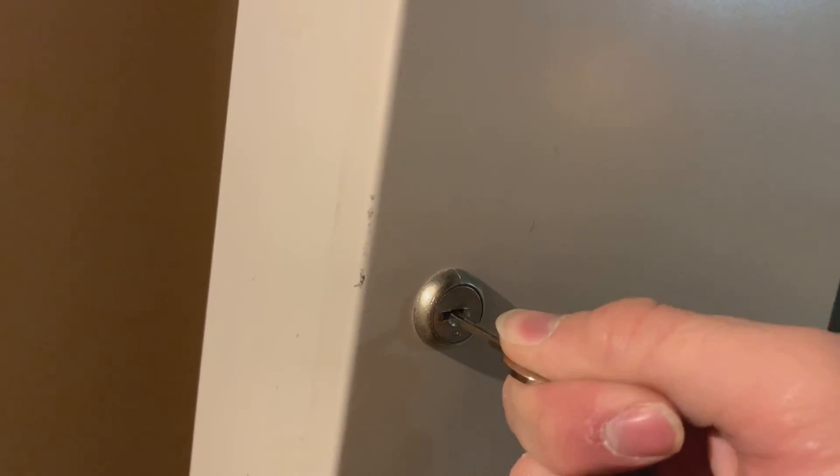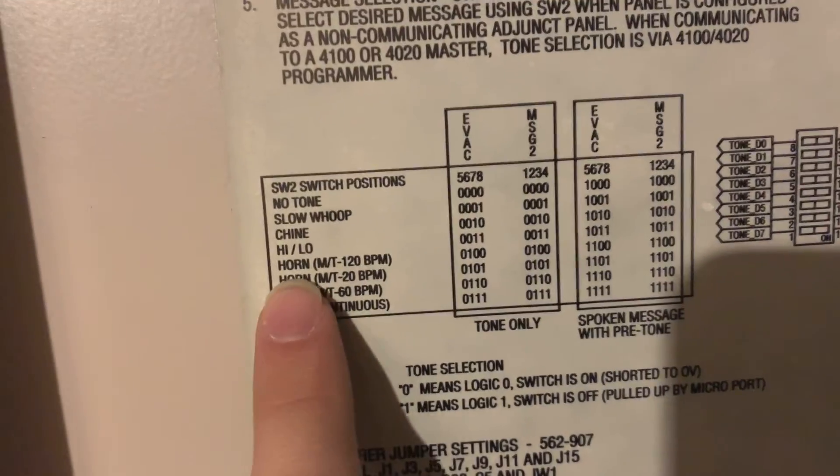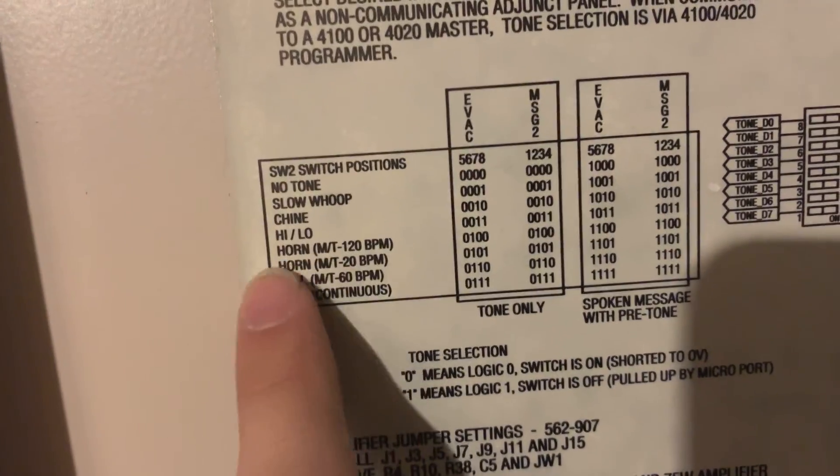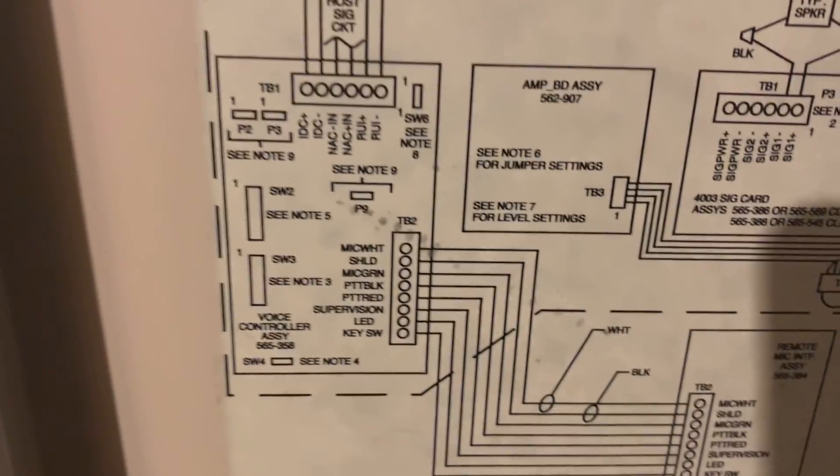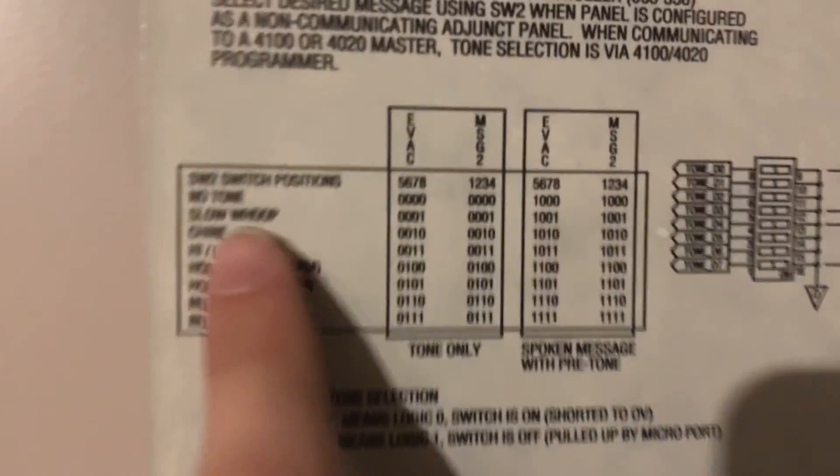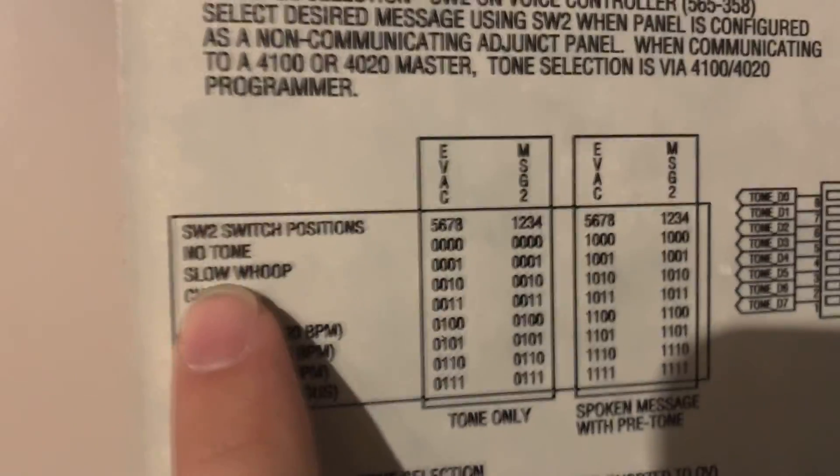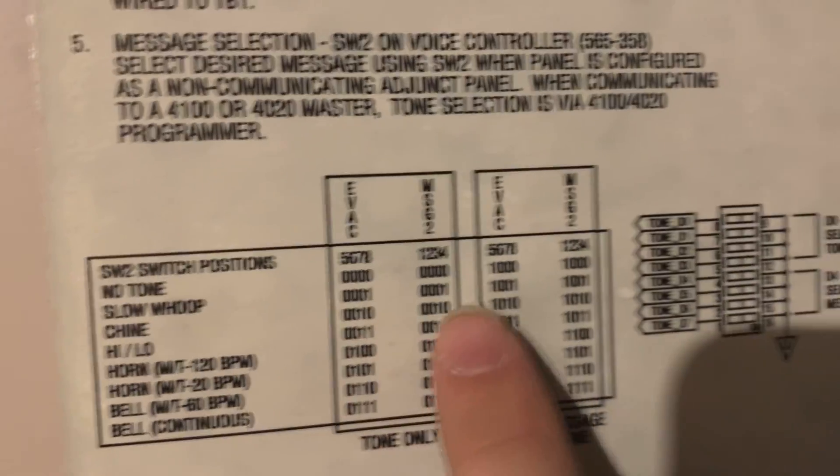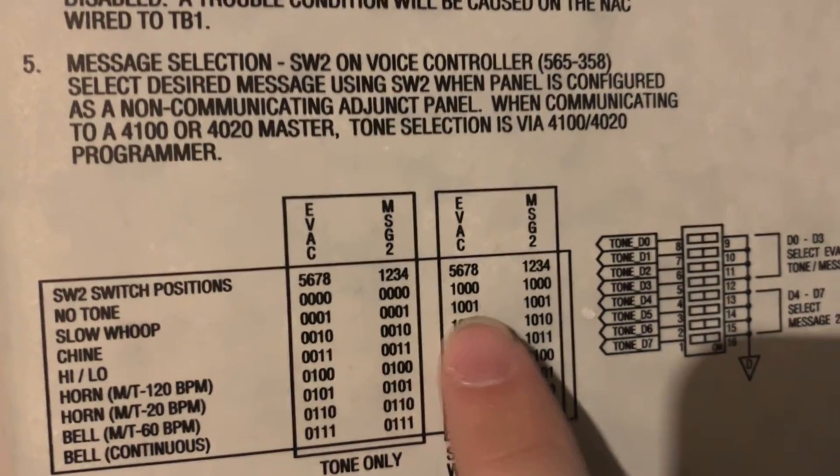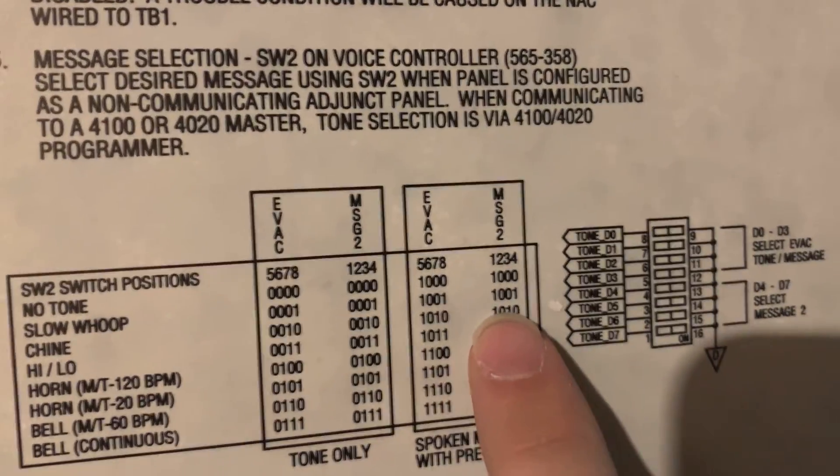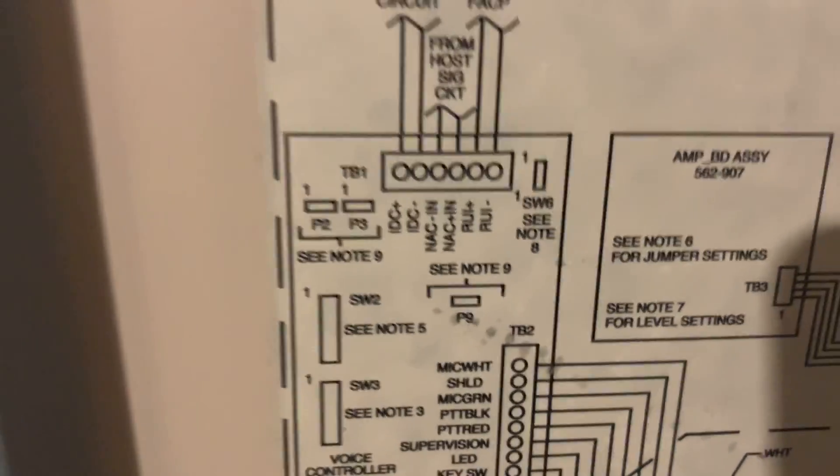One thing I actually meant to do before I got too ahead of myself here was set it to the slow whoop instead of that march time. What you heard was march time, 120 beats per minute horn. That's their horn sound. There's a little dip switch down here that's behind this thing. So I actually have to take this off again to set that. Your settings are in here. So if we want to do slow whoop with a message, it's 1001 on the eight things that are down here. So I'm going to set that real quick. Let's set it to slow whoop and then we'll continue the test.